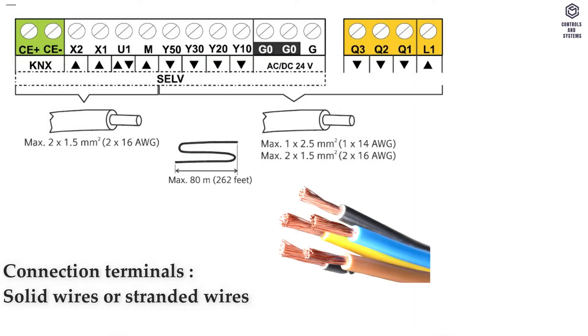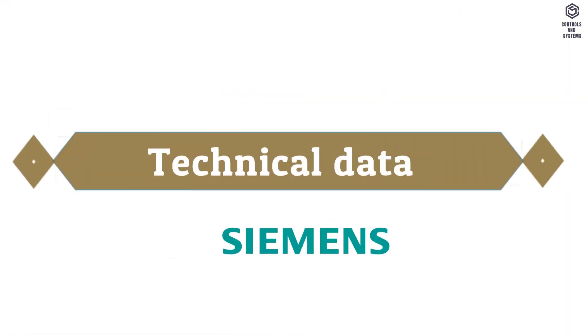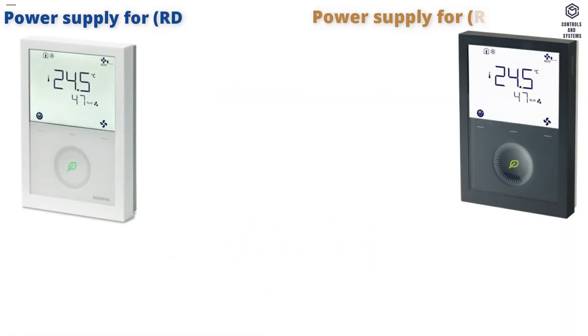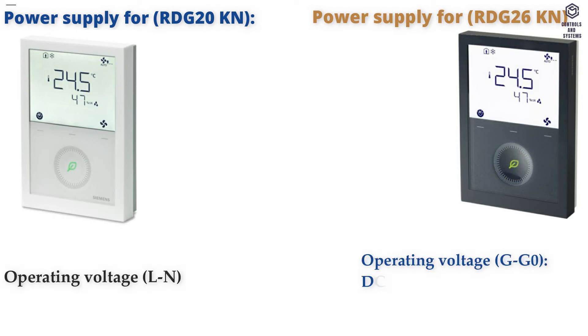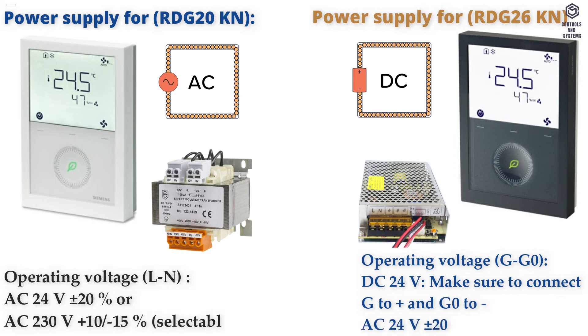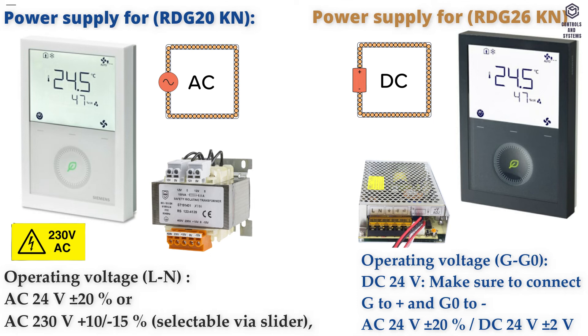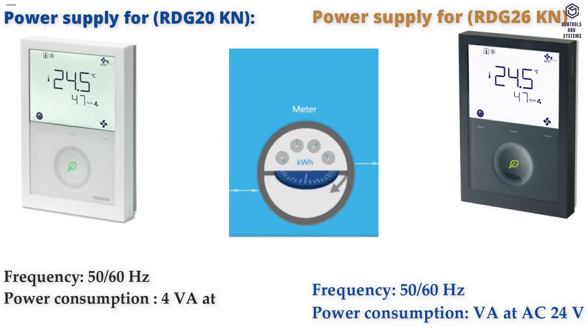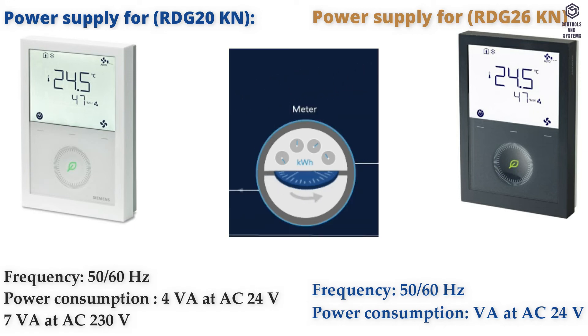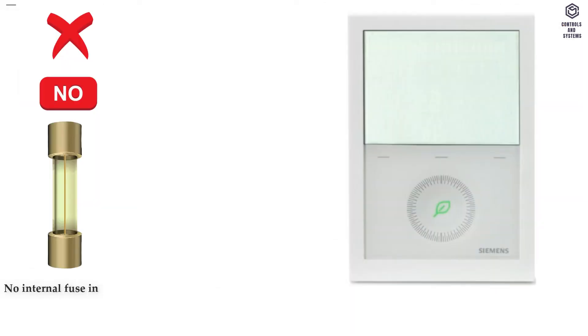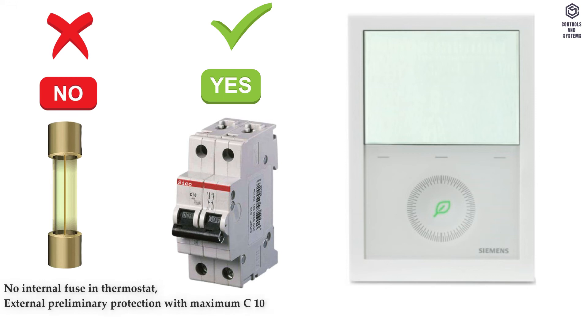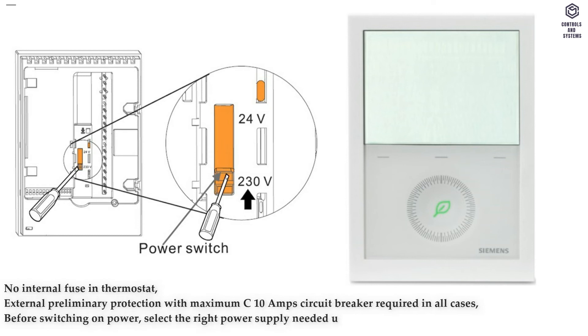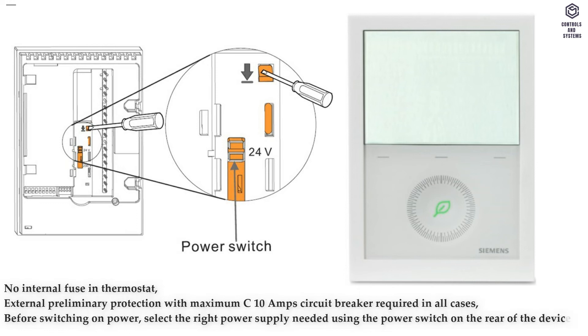Connection terminals accept solid wires or stranded wires with wire end sleeves. Technical Data — Power Supply for the RDG20KN model: Operating Voltage L&N is AC 24V ±20% or AC 230V +10/-15%, selectable via slider. Frequency is 50 or 60Hz. Power consumption is 4VA at AC 24V and 7VA at AC 230V. There is no internal fuse in the thermostat. External preliminary protection with a maximum C10 Amps circuit breaker is required in all cases. Before switching on power, select the right power supply using the power switch on the rear of the device.